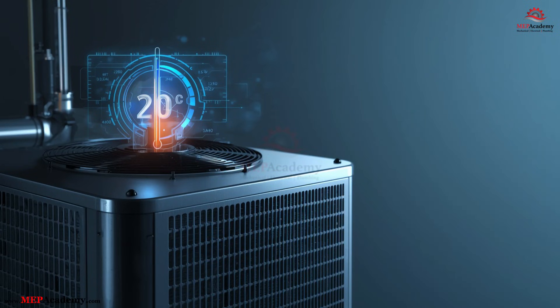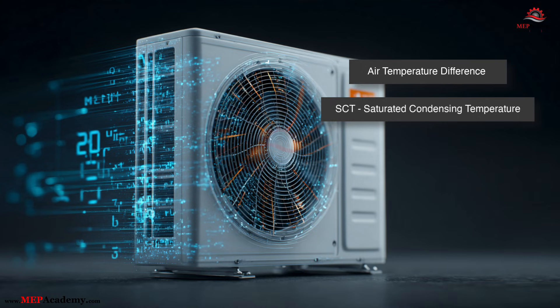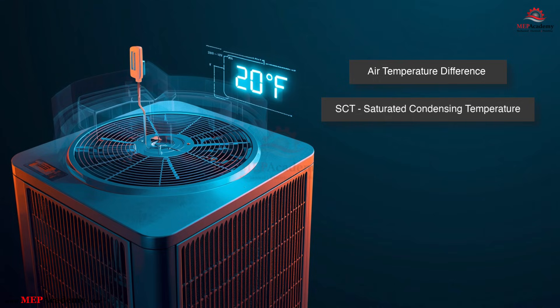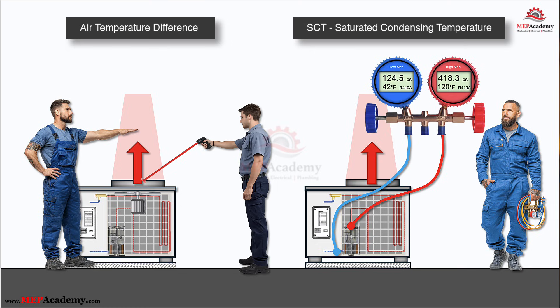When you're evaluating how well an AC condenser is rejecting heat, there are two common measurements technicians rely on: the airside delta T across the condenser coil and the saturated condensing temperature, or SCT, taken from the refrigerant pressure temperature chart. Both are valid diagnostic tools and both give you valuable information, but they measure very different things. Because of that, many techs confuse the two, or try to use one method to answer questions that belong to the other.